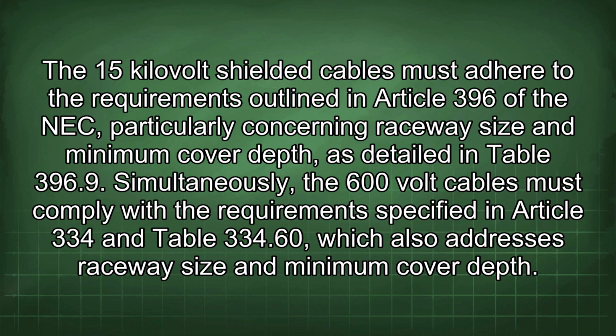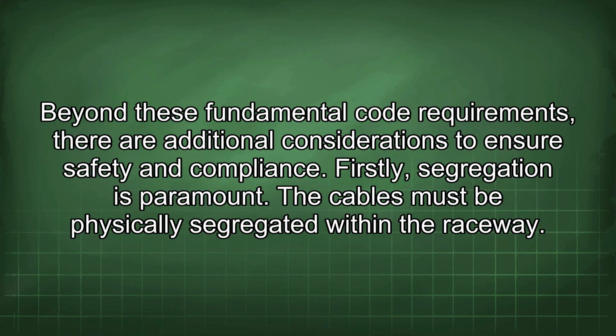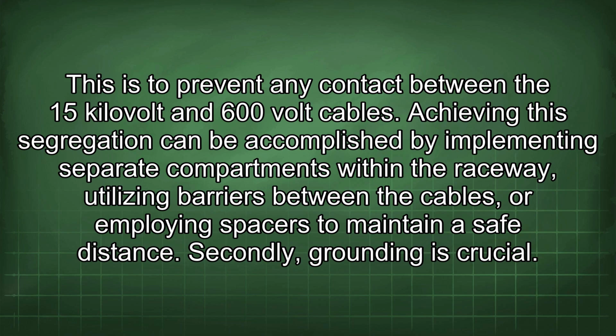Simultaneously, the 600 V cables must comply with the requirements specified in Article 334 and Table 334.60, which also addresses raceway size and minimum cover depth. Beyond these fundamental code requirements, there are additional considerations to ensure safety and compliance. Firstly, segregation is paramount. The cables must be physically segregated within the raceway. This is to prevent any contact between the 15 kV and 600 V cables. Achieving this segregation can be accomplished by implementing separate compartments within the raceway, utilizing barriers between the cables, or employing spacers to maintain a safe distance.